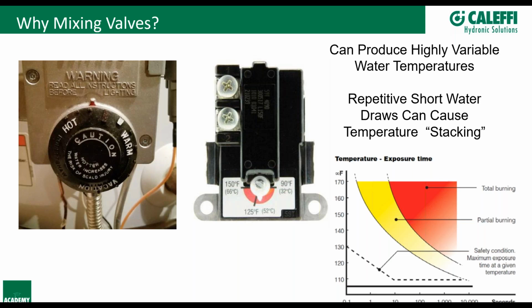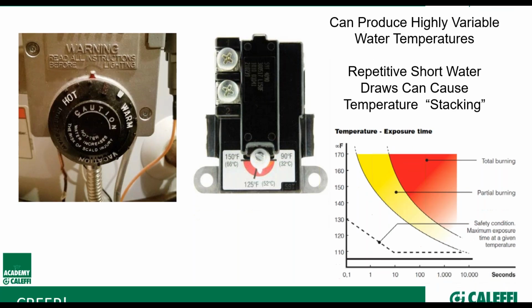hundreds of gallons of storage in a large commercial building, these aquastats or sensors or whatever, they're all going to have a differential or some form of hysteresis, and they're not always going to have the exact temperature all the time coming out at 120 or 125 or wherever you're looking at it. You can have 10 or 20 degree temperature swings, and that's where I think mixing valves really help the cause by making sure you have, like I said, a very consistent temperature coming out of that domestic hot water source to make sure you're protecting those occupants, and it's something that they're accustomed to, so that way they're not getting really hot sometimes and really cold other times.